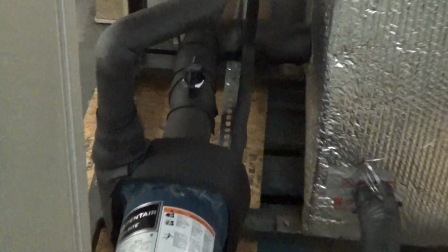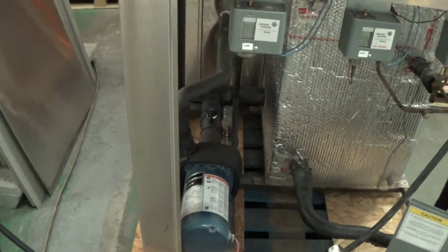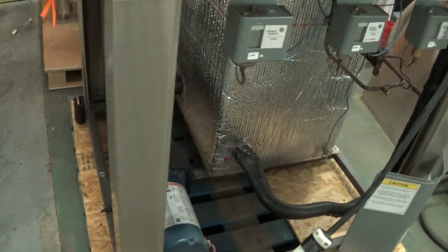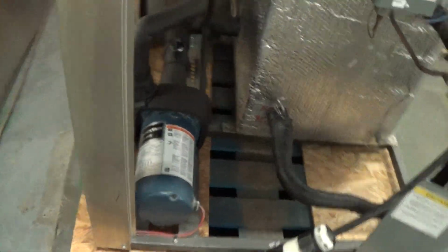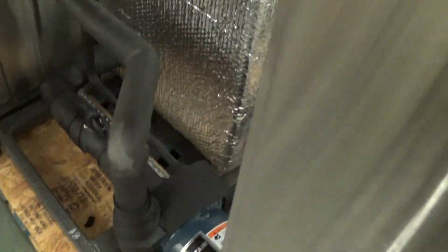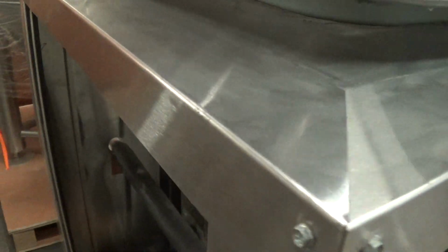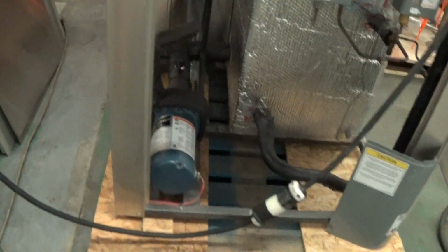You'll see a shut-off valve right there. That's to be left open at all times unless you're servicing the unit, because when it's running, you don't want to limit the pump suction at all. The Chill King chillers have an internal fixed bypass line. That's this third line you see going from the pump and up and back to the tank. So it's always bypassing a little bit of flow, so with the exception of very rare cases, you don't need to put on an additional flow bypass, which would be commonplace with other chillers.